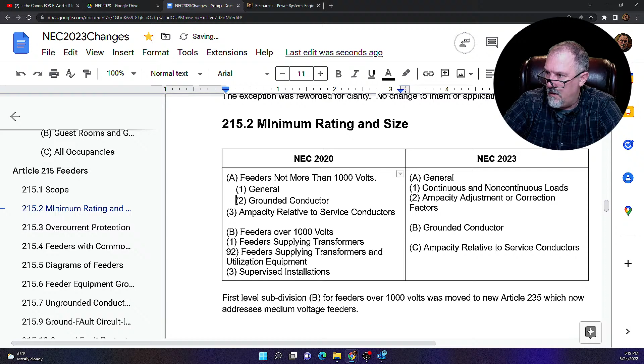So you had an A and you had a B. B went away, or moved. It didn't go away, it moved. General went to first level subdivision A. Grounded conductor went to first level subdivision B. Ampacity relative to service conductors went to C. And A was then, we had two second level subdivisions, 1 and 2.